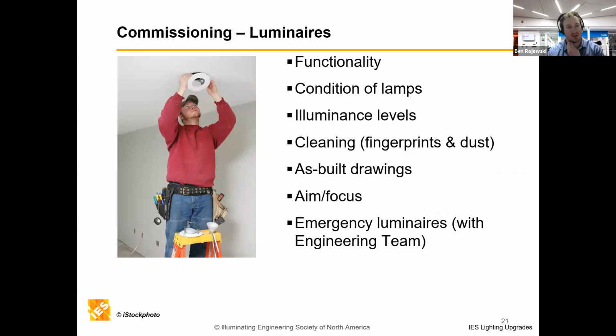Commissioning luminaires: first things first, is it working? Is the fixture on and operating like you expect? Is it giving you the light levels you expected, or is something causing it to be dimmed or not operating as expected? Does it look like it was installed correctly? Is it clean, flush to the ceiling, in the location you specified, and aimed at the target you want, if aiming is a possibility?